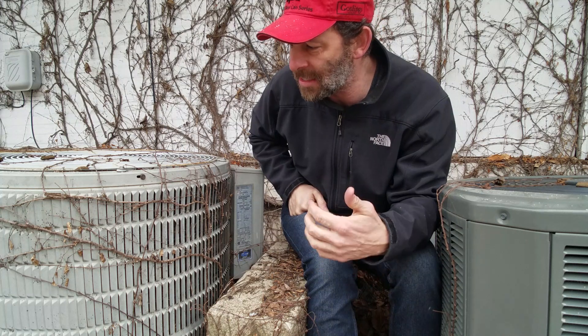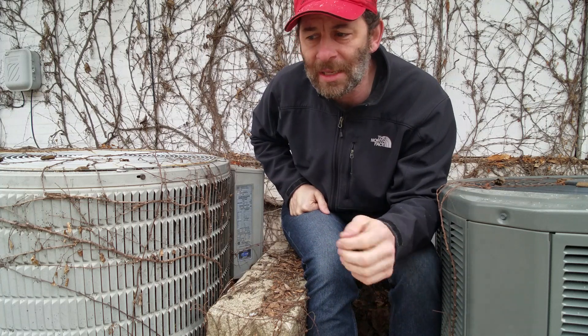That's how you look it up. And if you do have R22, it wouldn't be a bad idea to get an HVAC person out to take a look at the unit in the summertime, make sure it's functioning properly, and give you an idea of what remaining life they expect on that unit. I hope this helps you guys and keeps you from being surprised if you do have R22 refrigerant and you need some maintenance in the future — only to find out, surprise, you have to replace your unit. Hopefully this will avoid that situation.